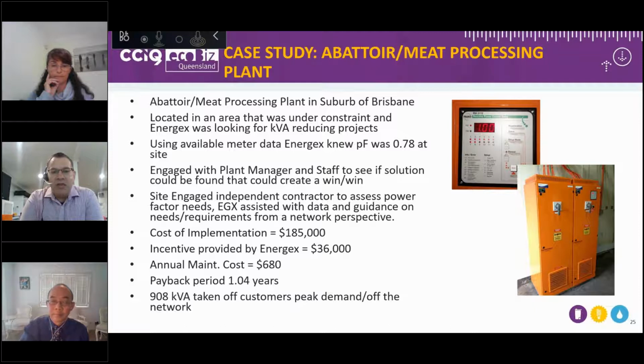This particular system as well has got an alarm system built into it, where if the power factor correction equipment stops working or trips out for any particular reason, and it can be something as simple as purely electrical reasons, or it could be something like a rodent getting into the wrong spot, it will alarm the relevant people, and they can come and reset it as quickly as possible. What I've seen is that this is where sometimes with maintenance or the active management of power factor equipment can fail, is that people set it and literally forget it. They don't put an alarm system in, and when it trips out, they don't find out about it until the following month, when their peak demand is sky high again, because they've been operating without the power factor correction equipment working for them.